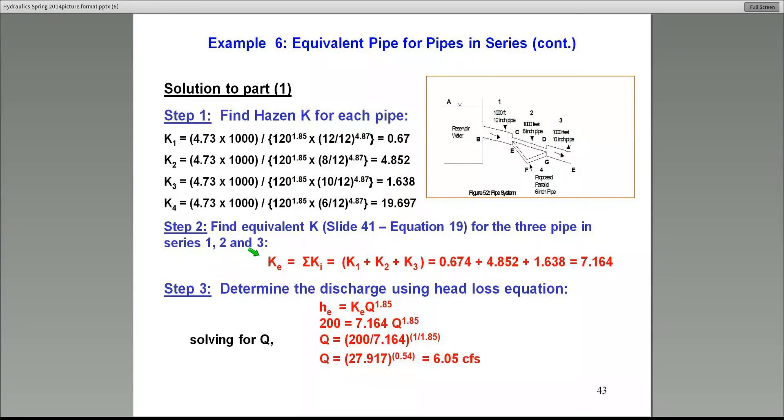Now that KE has several terms in it: it has a length, a C value, and a pipe diameter. So there might be an additional question asking what pipe would you select that has this equivalent KE. In that case, you have to know the C value and the length of the pipe also. Those have to be pre-specified because there are three unknowns in that equation.